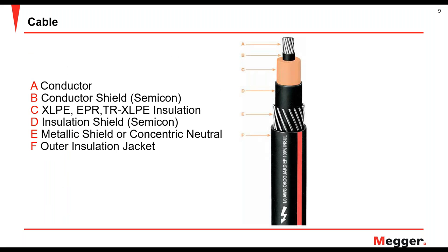Next, we're going to be moving to cables. This is a cable similar to what most people use. First, you have your center conductor — in this case, aluminum. Then you have your conductor shield or semi-con, then your insulated medium, which is EPR in this case. Then you have your insulation shield, then your metallic shield or concentric neutral. Finally, you have your outer jacket of the insulation if you have one.